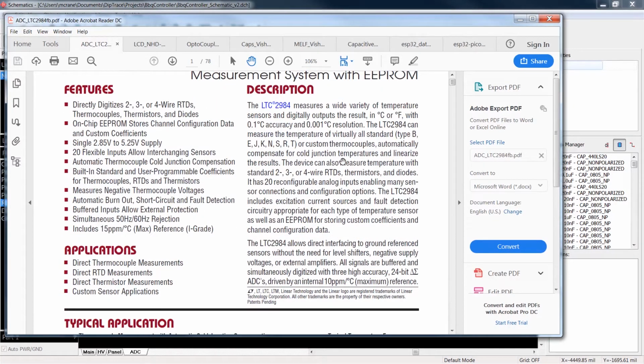This thing is nice. Check this out, this is definitely the duck's guts right here. It measures a wide variety of temperature sensors and digitally outputs the results in degrees Fahrenheit or Celsius at 0.1% or 0.1 degree C accuracy, with 0.001 degree C resolution. The 2984 can measure temperature of virtually all standard Type B, E, J, K, N, S, R, T, or custom thermocouples, automatically compensates for cold junction temperatures, linearizes the results, and can measure temperatures with standard 2, 3, or 4-wire RTDs, thermistors, and diodes. It has 20 reconfigurable analog inputs that you can swap around, and it includes excitation current sources, fault detection, and so on.